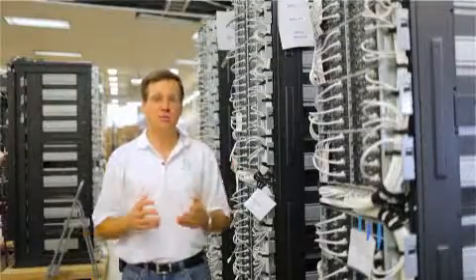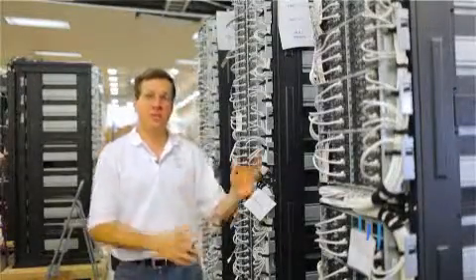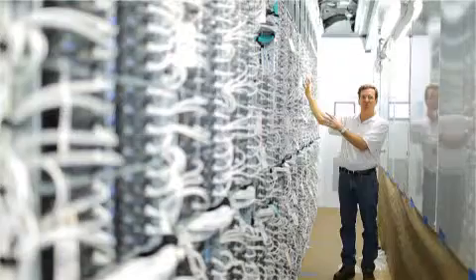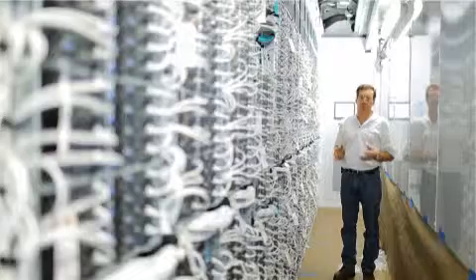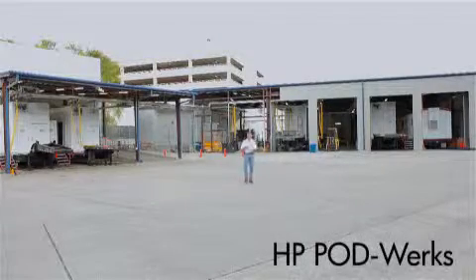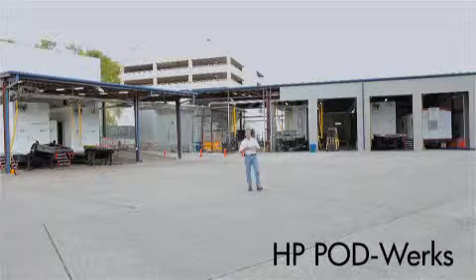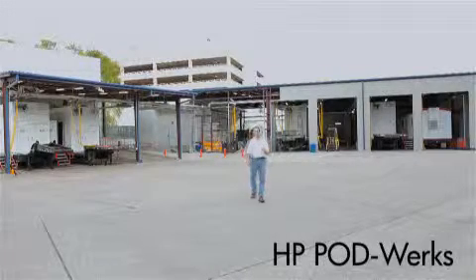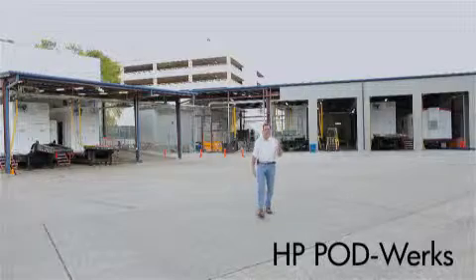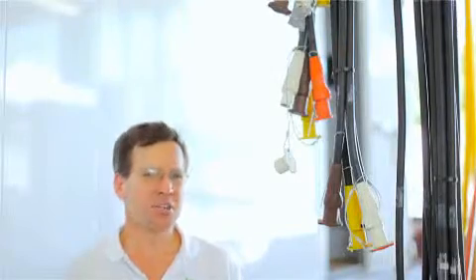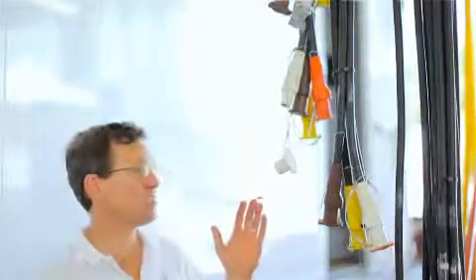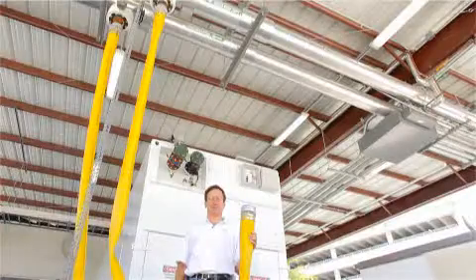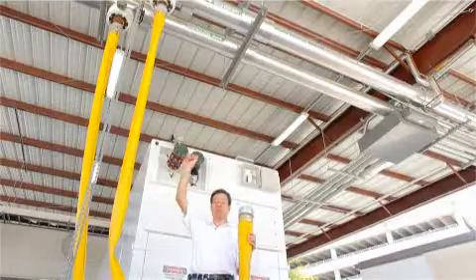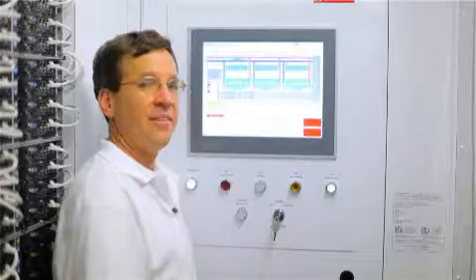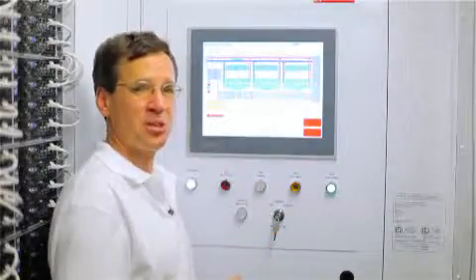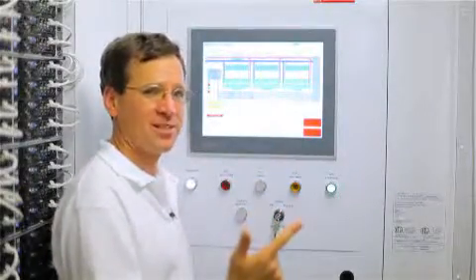It doesn't matter how you use those 1 to 3 megawatts, whether it's as 130 kilowatt racks or 8 kilowatt racks. What matters is converging this infrastructure into modular, scalable, industrial components, so you're free to decide how to use your assets of people, time, power, and money. These converged components consist of power feeds coming from the 4,000 amp backplane, water feeds coming from the modular chillers or central chiller plant going into your pods, and the control and safety systems to ensure your data center is always on and always optimized.